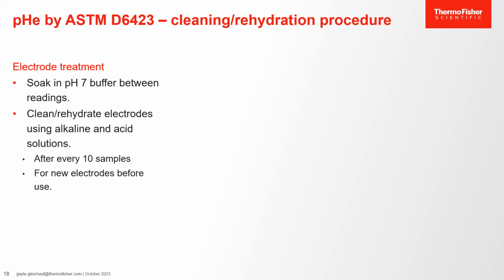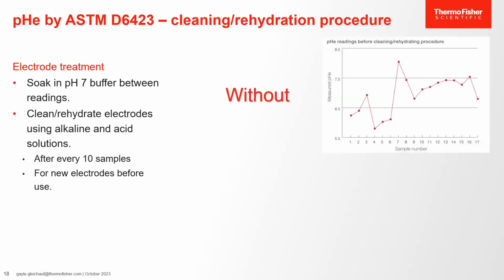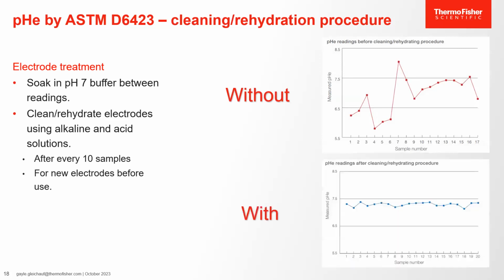During the interlaboratory study in our lab, we found that this cleaning rehydration procedure is indeed a necessary step to preserve the electrode's performance characteristics. Without this procedure, PHE readings are not consistent or reliable, as seen in this chart. Readings of the same sample can change from less than pH 6 to about pH 8. But with the cleaning rehydration procedure, repeated PHE readings become very consistent and reliable, as seen in the bottom chart. The cleaning rehydration steps greatly improve the performance and the PHE readings, and they're well worth the effort.